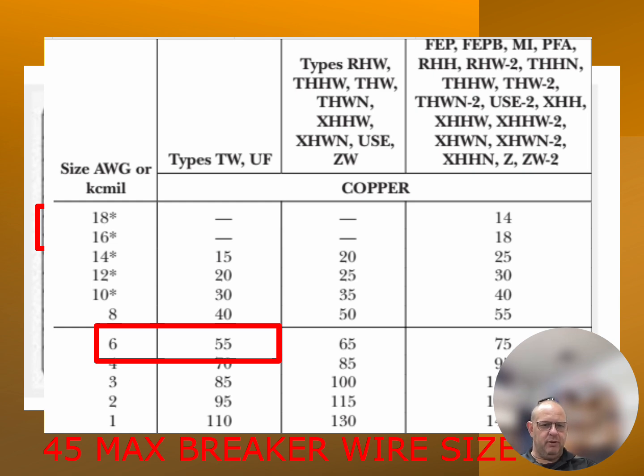Will the breaker trip before it hits 55 amps? Yes. So the breaker will protect the wire from burning up. And we base that off of our NEC constant running amperage of 43 amps. I'm going to put a 45 amp breaker in there, go to the NEC amp chart to find out what type of wire I need to install, and I end up installing a 6 gauge wire. I hope you understood that. If not, send me an email. If not, ask me questions in the classroom. I will walk you down this particular process.